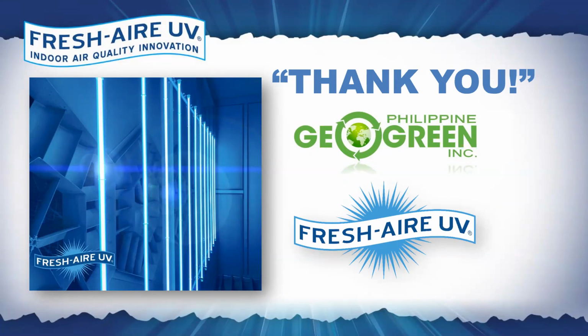Yes, we have done the testing, a lot of it actually, with many different time points, and as mentioned, this was not on a surrogate but on the actual SARS-CoV-2 virus. The real challenge was that, being one of the first companies able to attain SARS-CoV-2 testing, we were not able to do an aerosolized duct test. That was an issue because people want to see how effective these systems are in duct systems, since ours are mounted in ductwork, but that was just not possible at the time.